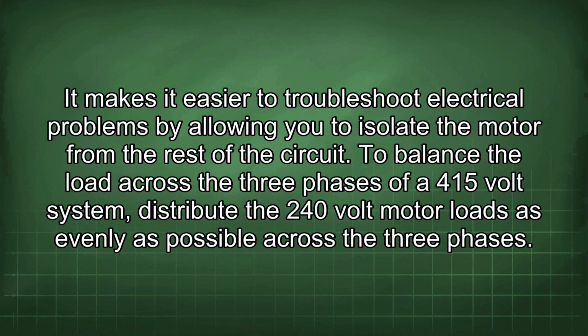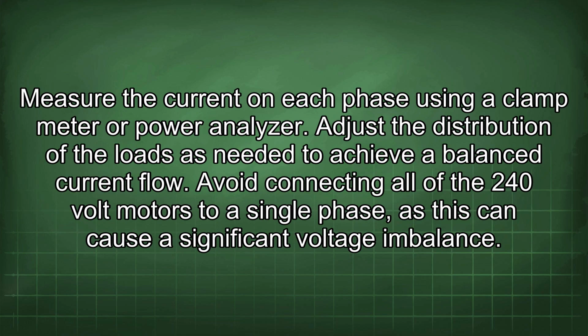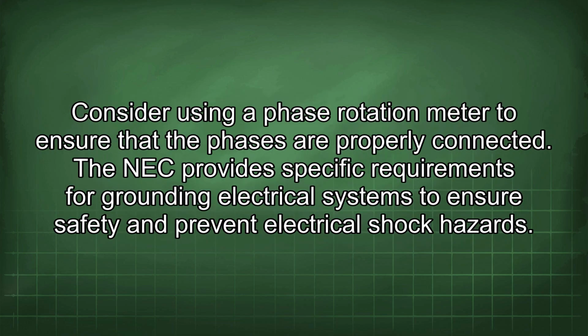To balance the load across the 3 phases of a 415-volt system, distribute the 240-volt motor loads as evenly as possible across the 3 phases. Measure the current on each phase using a clamp meter or power analyzer. Adjust the distribution of the loads as needed to achieve a balanced current flow. Avoid connecting all of the 240-volt motors to a single phase, as this can cause a significant voltage imbalance. Consider using a phase rotation meter to ensure that the phases are properly connected.